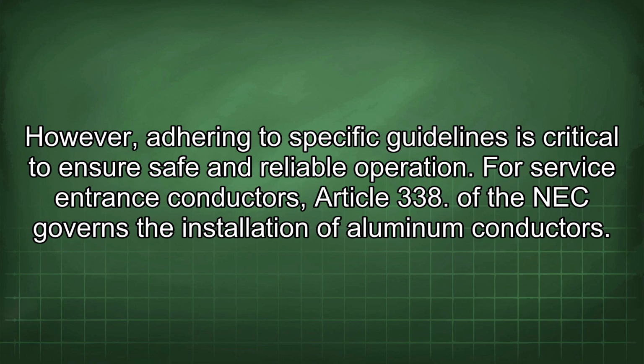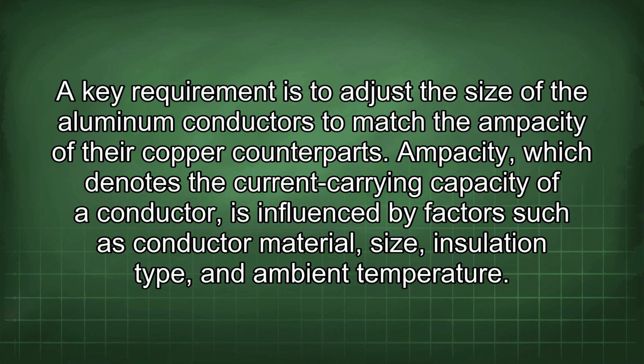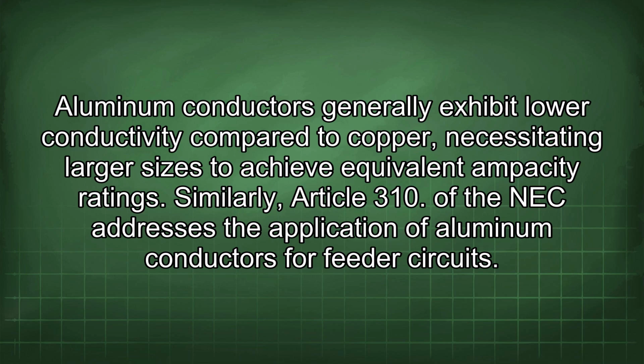For service entrance conductors, Article 338 of the NEC governs the installation of aluminum conductors. A key requirement is to adjust the size of the aluminum conductors to match the ampacity of their copper counterparts. Ampacity, which denotes the current carrying capacity of a conductor, is influenced by factors such as conductor material, size, insulation type, and ambient temperature. Aluminum conductors generally exhibit lower conductivity compared to copper, necessitating larger sizes to achieve equivalent ampacity ratings. Similarly, Article 310 of the NEC addresses the application of aluminum conductors for feeder circuits.